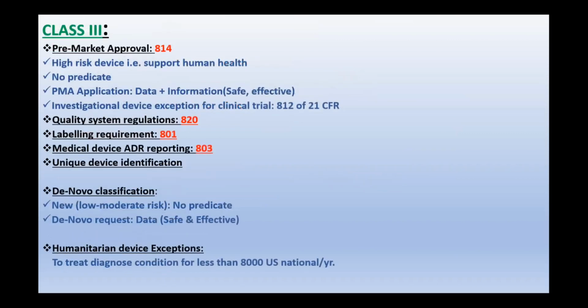For class 3 medical devices, the pre-market approval process is needed, which is listed in part 814 of 21 CFR. For high-risk devices that support human health, for which no predicate device has already been marketed in the country, the pre-market approval application has to be submitted along with the data and information proving it safe and effective.